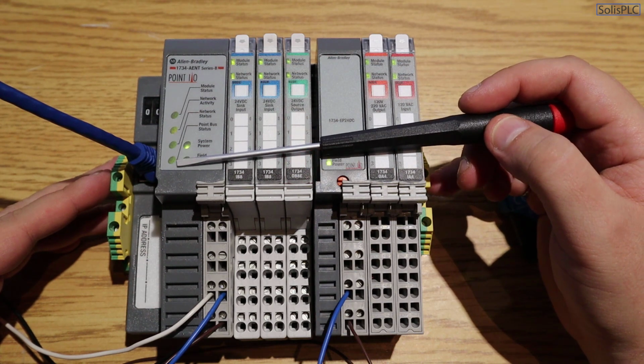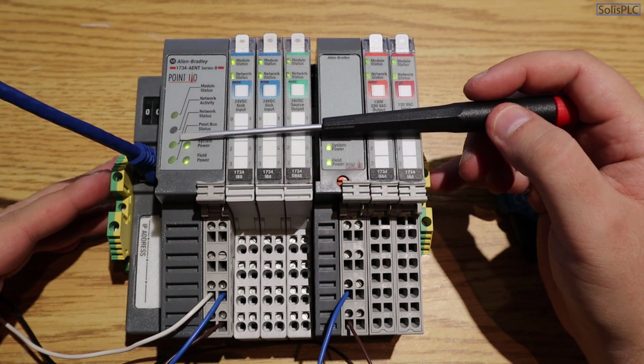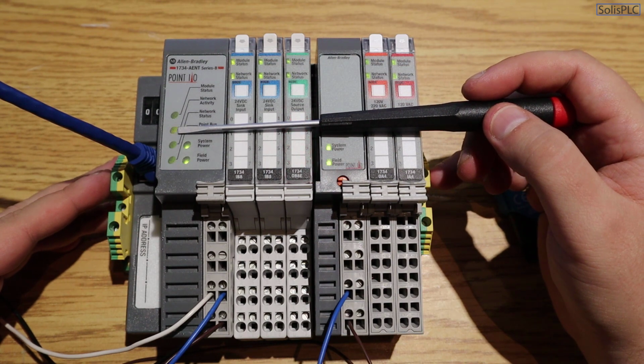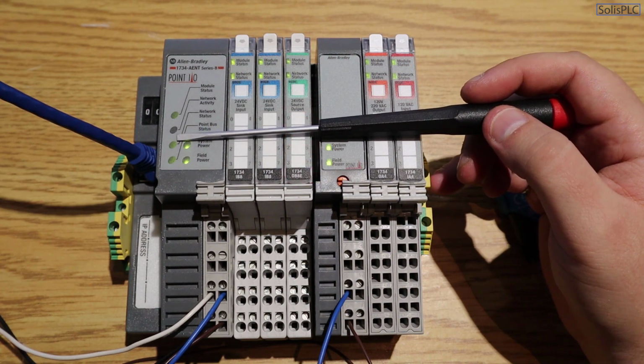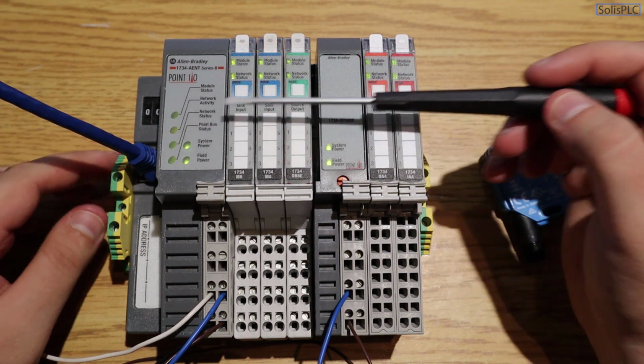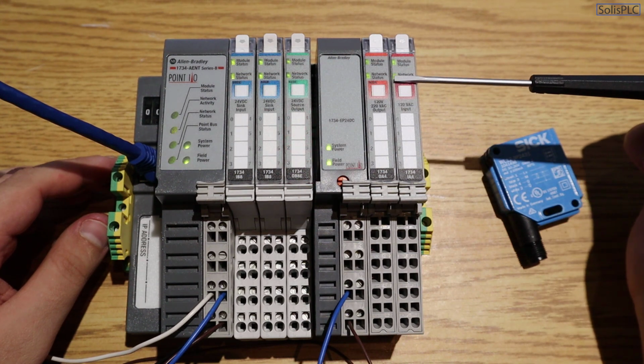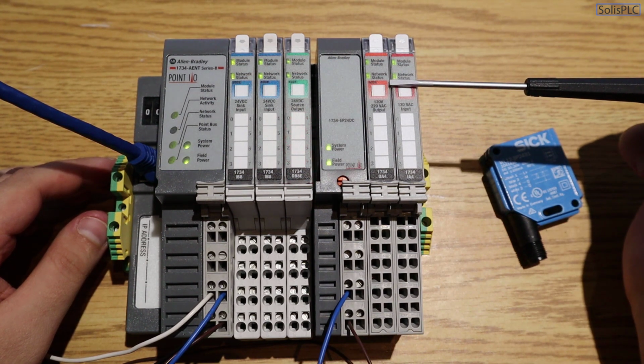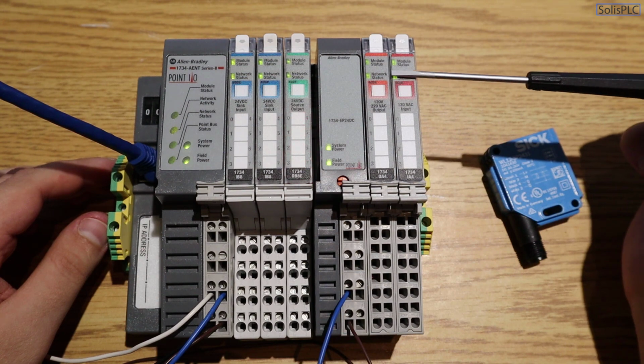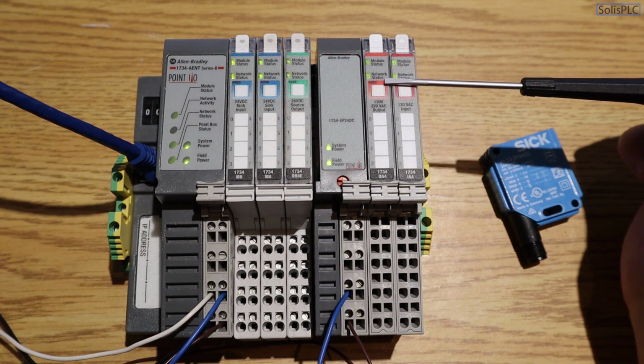So you'll notice that the light down here is green. It's also green here, and we have network traffic. So it's definitely communicating back to the CompactLogix PLC. You'll also notice that the two lights for the rightmost modules are also green on the network side. So this means that they have been properly configured and everything is ready to go.